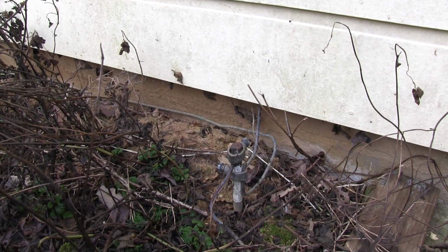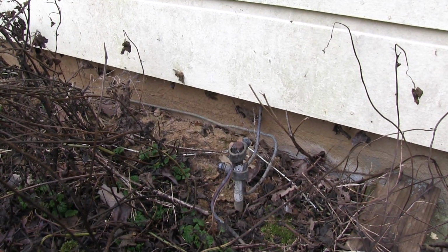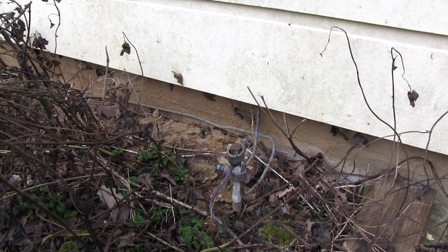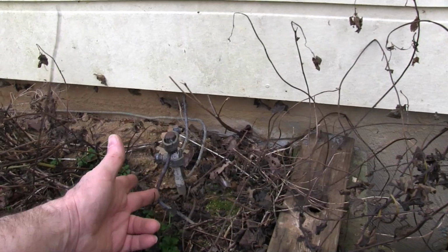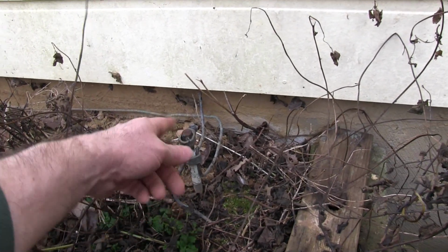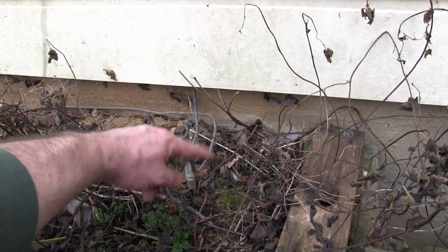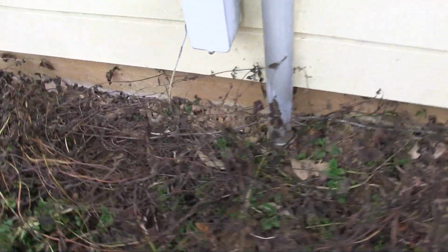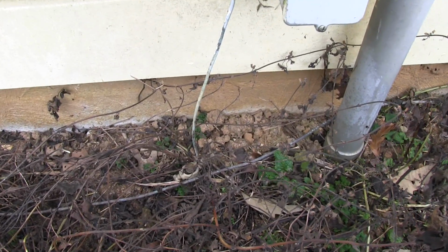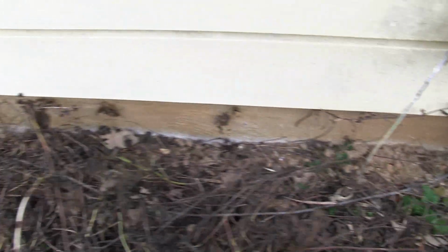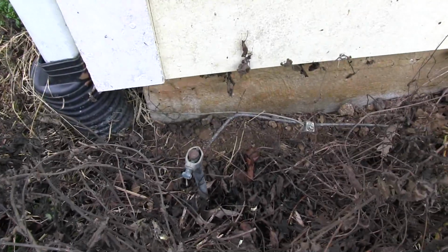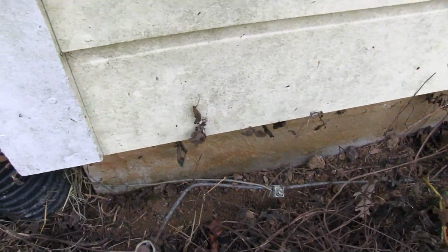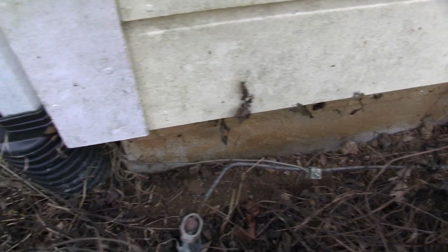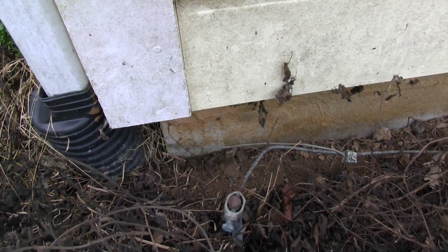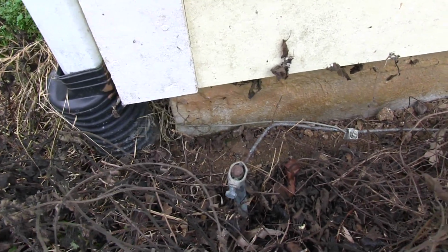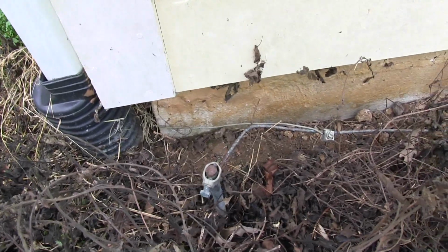So I put in oversized ground wires and 2 copper clad ground stakes. This wire goes to my antenna, which is also grounded, and then that goes into the fuse box you can see going on the house. This one goes over here, bypasses another ground stake. That one grounds the meter, and it comes over here to another ground stake that I put in. AT&T grounded the phone lines where they come in. So anyway, the grounding rods are more than 6 feet apart. Here's 2 of them. I have oversized ground wire.